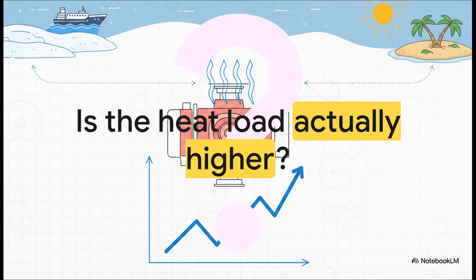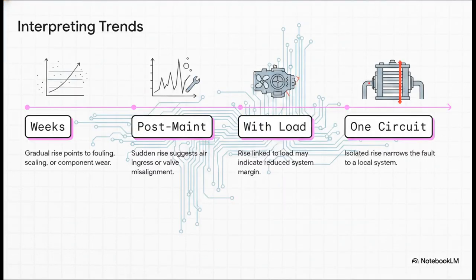Are we sailing out of the cold North Atlantic and into the Caribbean? A change in the environment or operation can cause temperatures to rise. It doesn't mean you ignore it, but it's a critical piece of the puzzle. This is how you read the story that the trend is telling you. A slow, gradual rise over several weeks? That points to fouling, or maybe pump wear.